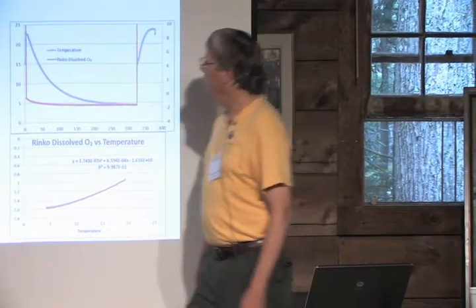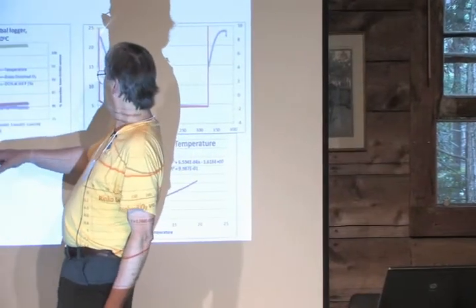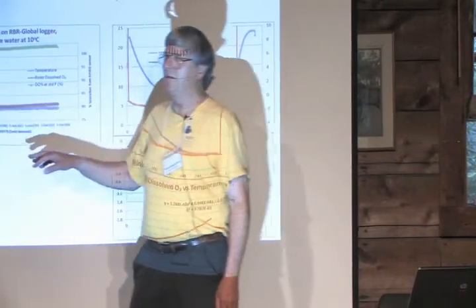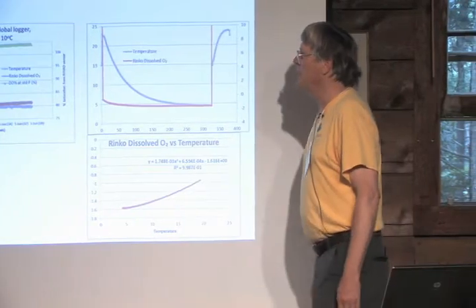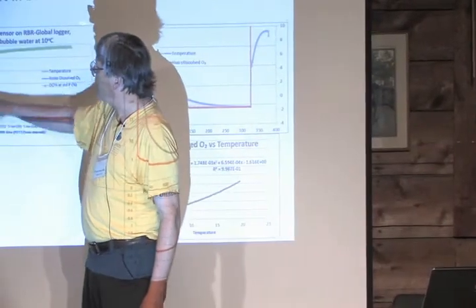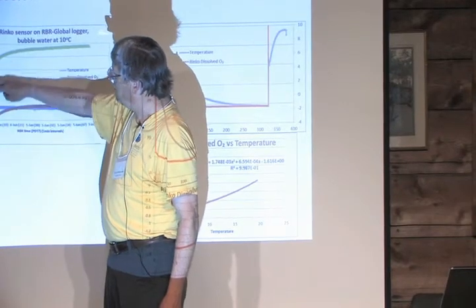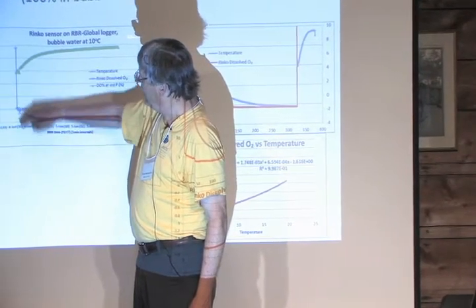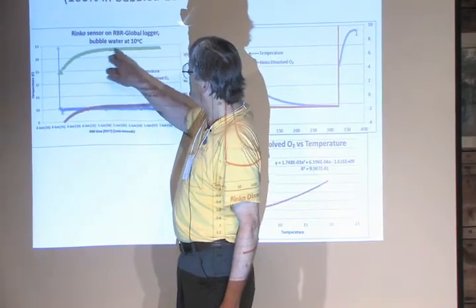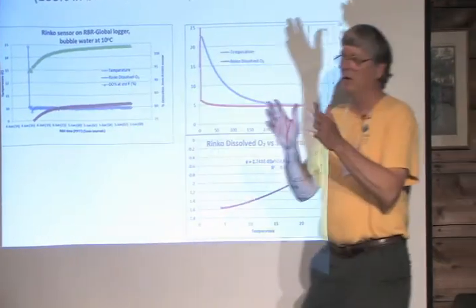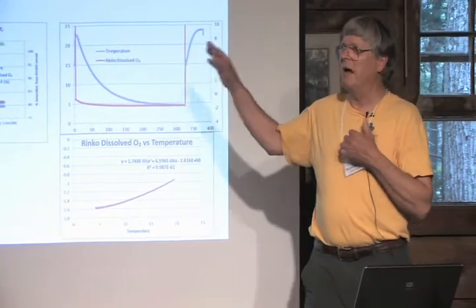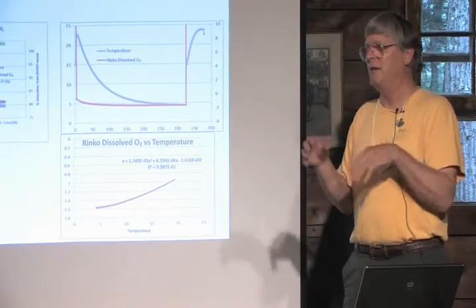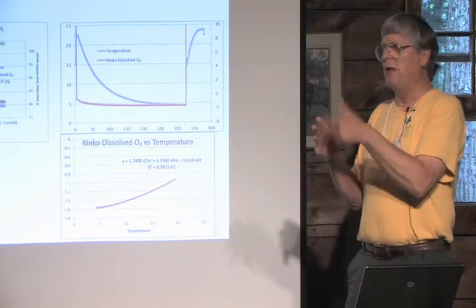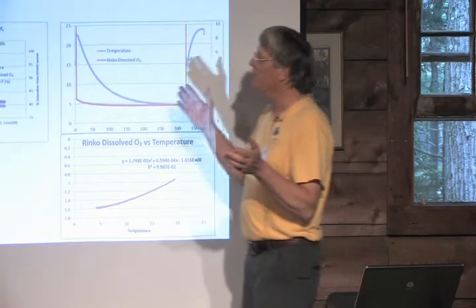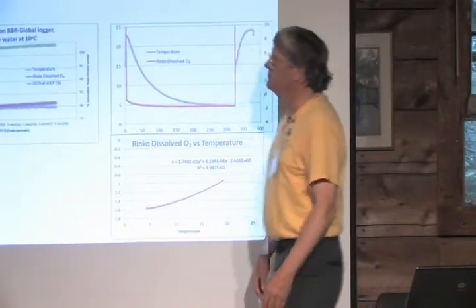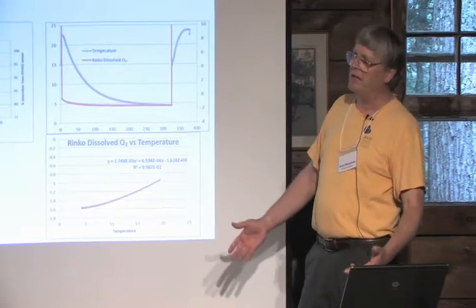What's the temp horizontal scale? I can't see that there, but that's basically 2 days. So it was easier just to leave it for a day or two and let it run because this took about, I think I started the bath, the bubbler, right at the beginning here, and that was the problem. So it takes about a day, actually. Big bath, small bubbler, 2 bubblers. I would actually prefer that we're now changing this to use a small container bubbled in a larger bath. The outer bath controls the temperature of the inner bath, but you don't bubble all that water. It's quicker. But whatever method you use, you need to wait till it's stable and not just say it should be 30 minutes, because I think it should.